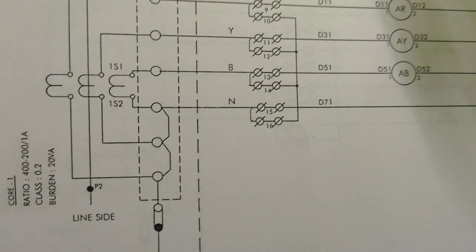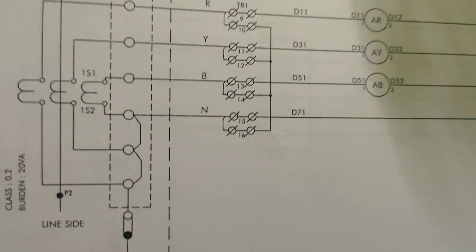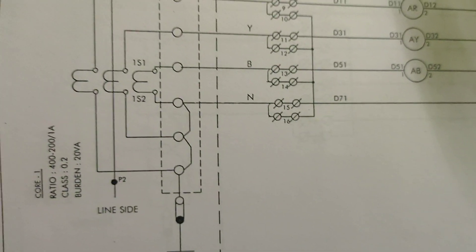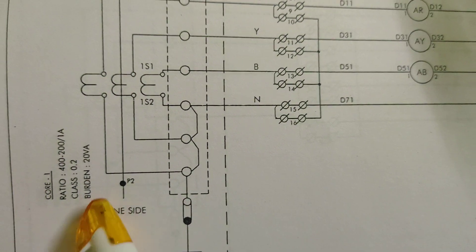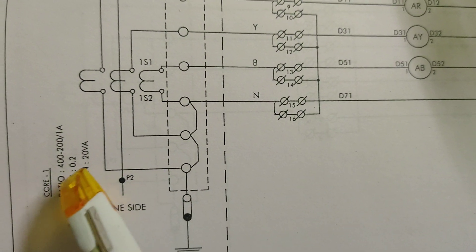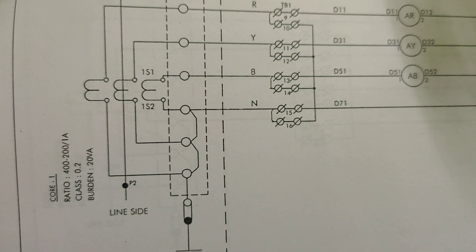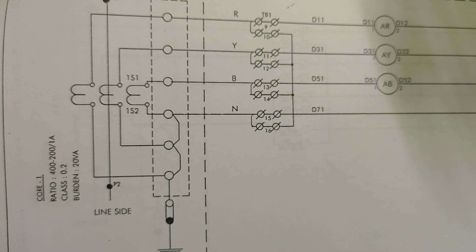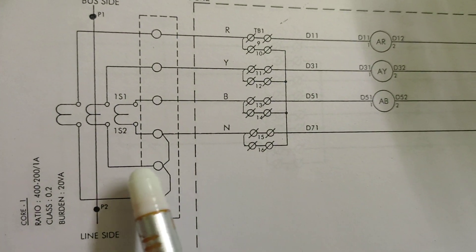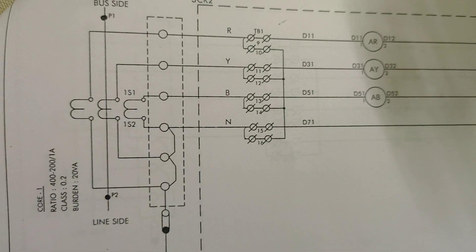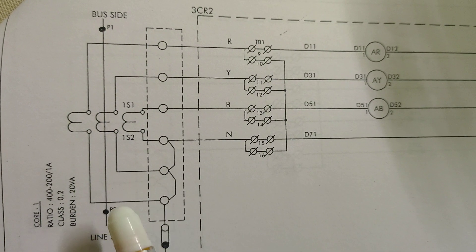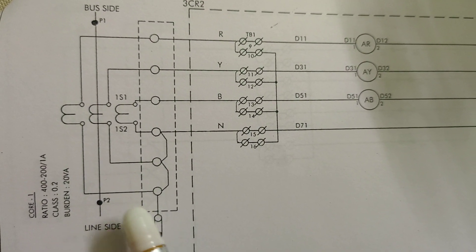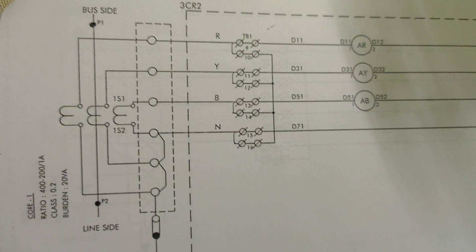Today I am considering a CT of 400/200/1, class 0.2, burden 20VA. As we are discussing the metering circuit, we consider core 1. Core 1 of the current transformer is used for metering purpose — it is accuracy class 0.2.